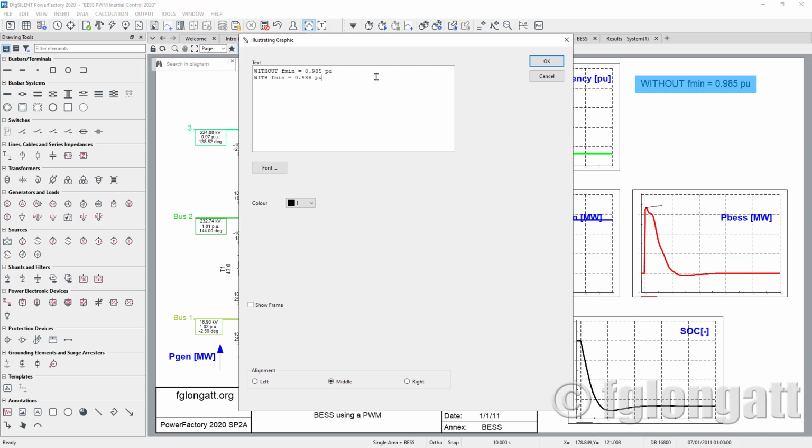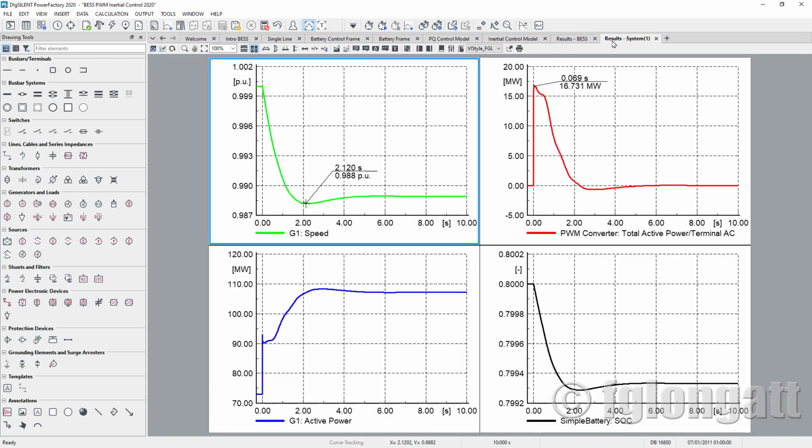Okay, what I can tell you is this frequency controller is working. This frequency controller is helping. Of course, it's not helping so much, and I will tell you later the reason, but the inertia controller is not so strong helping the minimum frequency. But coming back here to my explanation, this is one of the advantages of enabling frequency response in this battery energy storage.